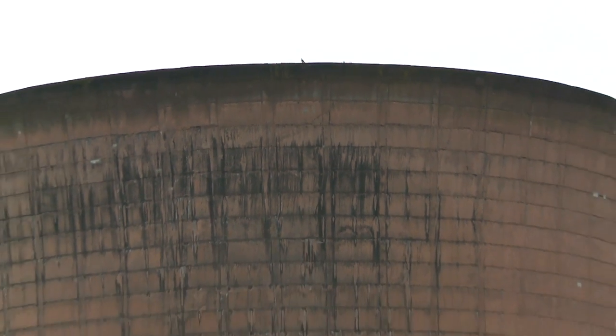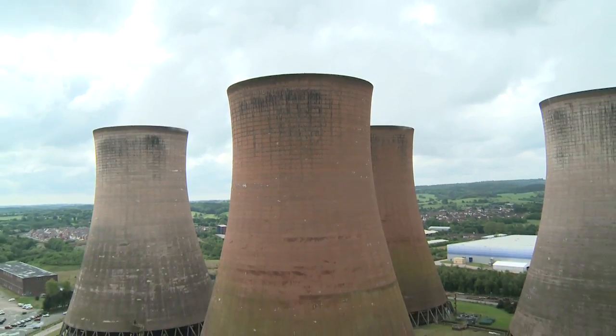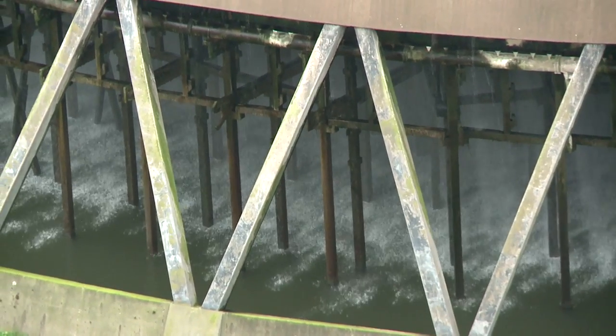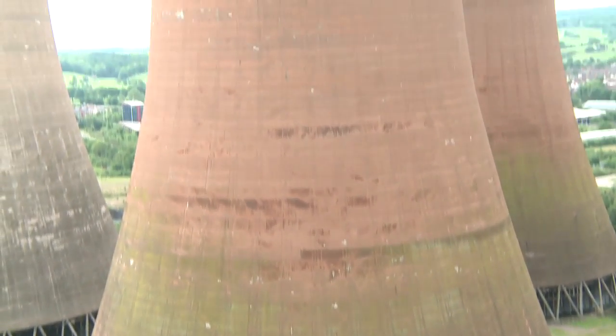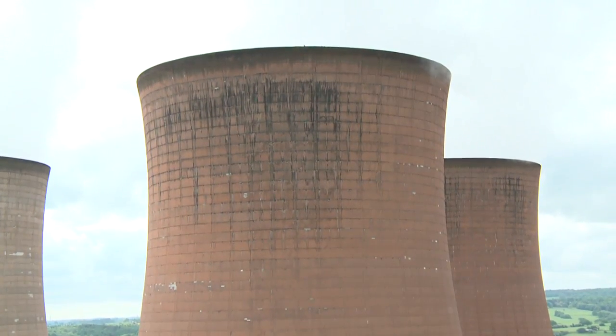You need vast quantities of water. You can see the cooling towers. The water from the condensers, which started from the Trent, gets slightly warm. To recirculate it for reuse, we sprinkle it in the bottom of those big concrete cooling towers. They are shaped as they are to naturally pull in draught at the bottom. As it rises up these tall structures, it cools the water that's sprinkled from about 10% of the way up, and that cooling allows the water to be pumped back to the condensers.